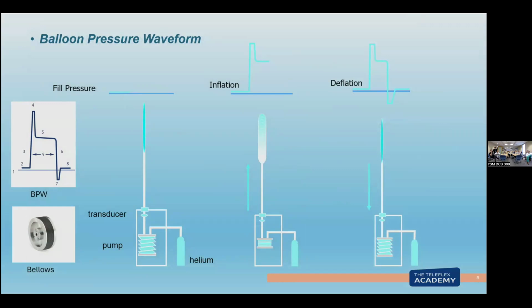Now, again, this is how it's created. We are not a vacuum compressor system. We are a motor driven bellows. So the bellows opens up to fill for the size of the balloon. So if I've got a 40 cc balloon, it opens up for 40. All of the dead space in our pump and tubing is the same, no matter what size balloon you put in. So when we plug in our balloon catheter, because it has a connection that tells the pump the size of the balloon, the bellows opens up for that size.